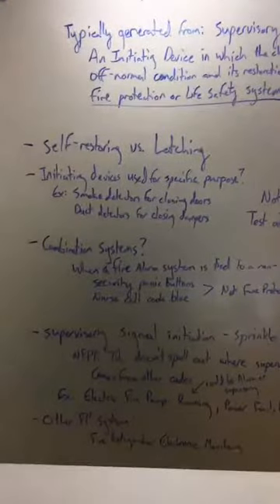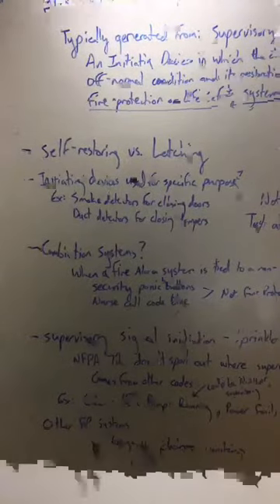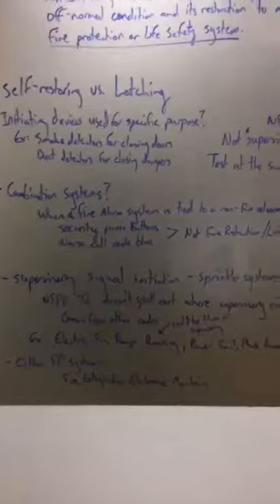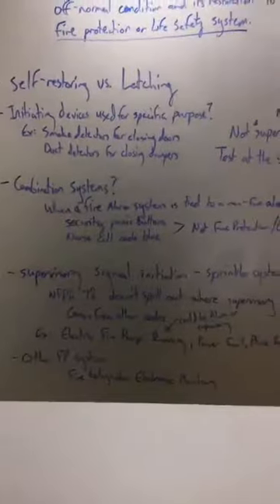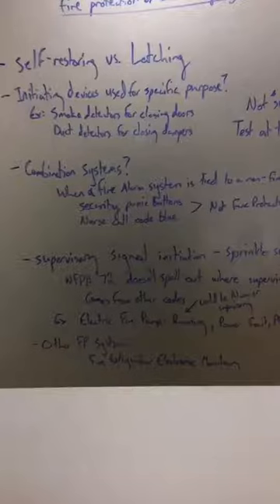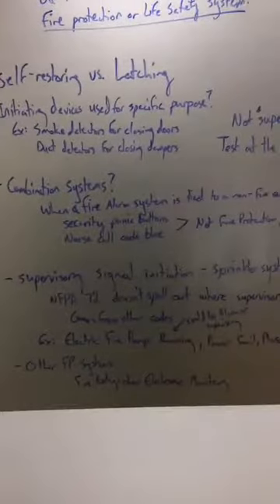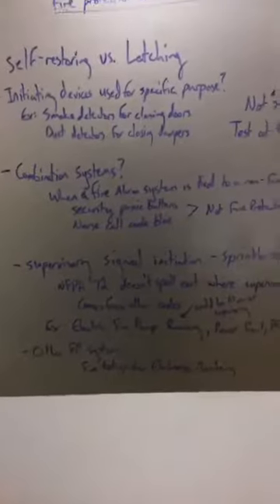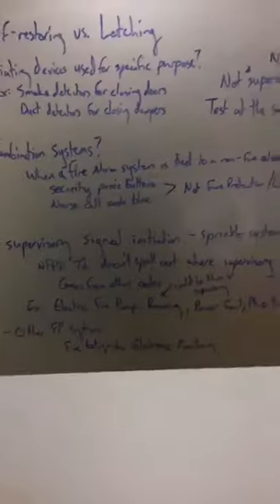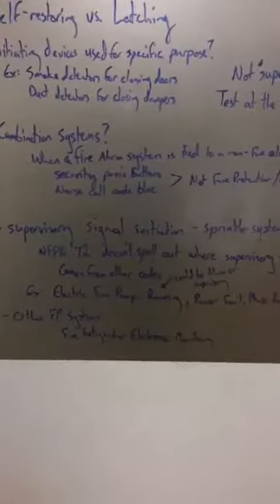And then supervisory signal initiation for sprinkler systems. NFPA 72 does not specifically spell out where supervisory signal initiating devices are required for sprinkler systems. This comes from other codes. So NFPA 101, NFPA 20 will tell you. So you need to know when your system was installed and reference the appropriate code of what's required. Older systems, like one of our hospitals has a 40-year-old electric fire pump. We don't have any supervisory signals on it.